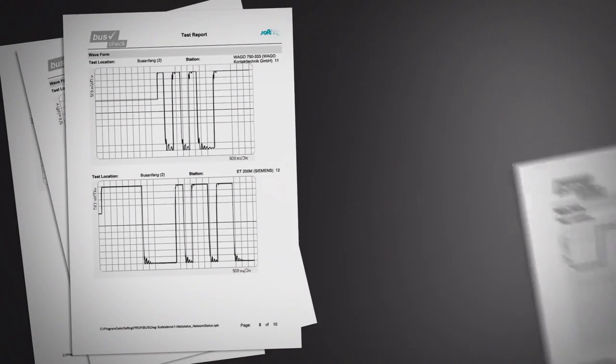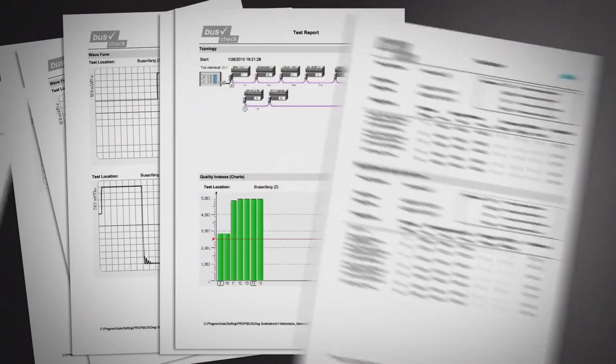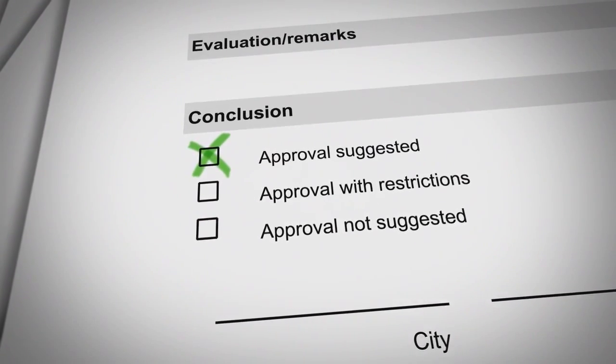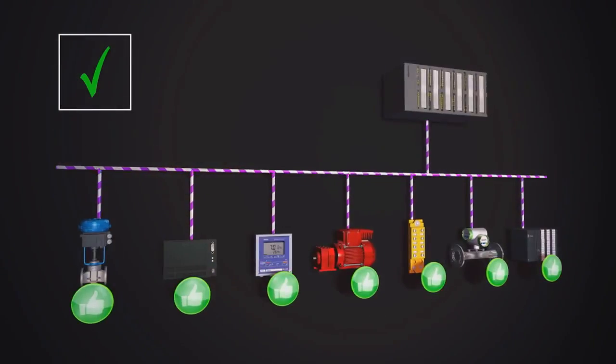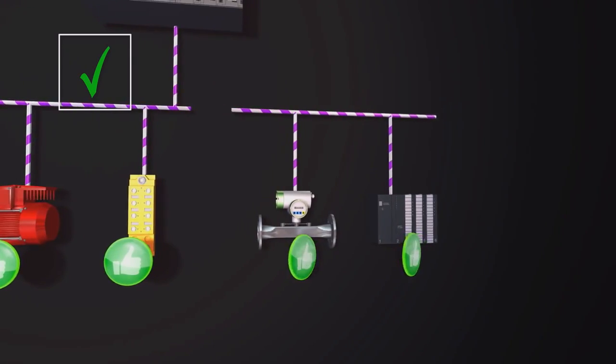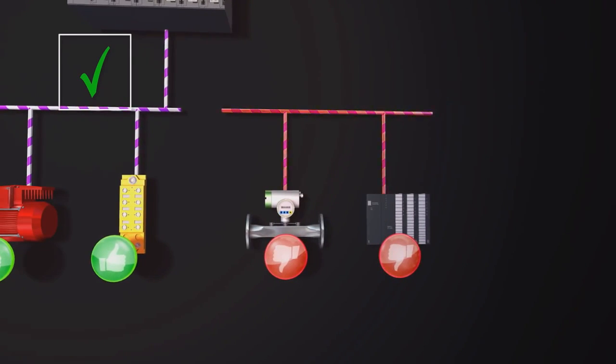A detailed test report can be generated to document the bus status. The report provides all the details on bus physics and bus communication, including live list, diagnostics, signal quality, oscillograms and topology. If a bus problem occurs after all, rapid pinpointing and troubleshooting is essential.